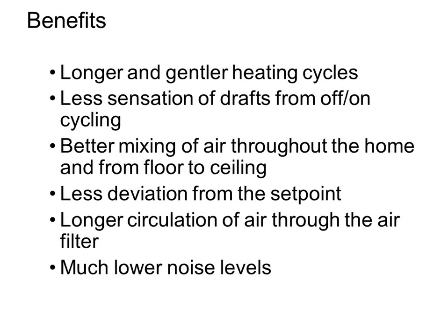I'm going to be able to keep pretty tight set point control, generally within 1 or 2/10 of a degree. So a normal thermostat, if I ask it to provide me 72 degrees for heating, it probably is going, when I drop down to 71 degrees, it turns on the heat. It heats the space till it gets to 72. Then it shuts the heat back off. It lets it drift down to 71. Then it turns it back on. That's a pretty normal thermostat.